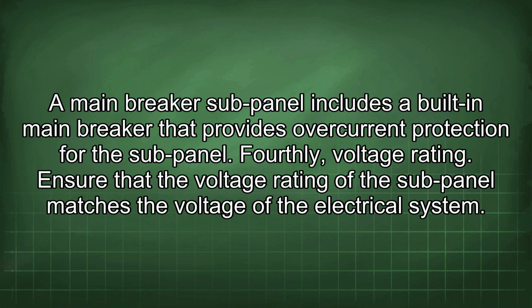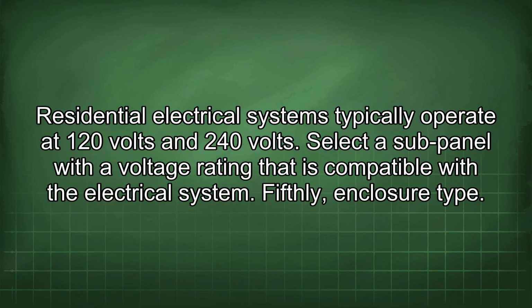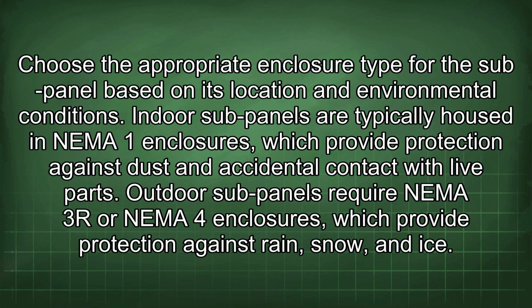Fourthly, voltage rating. Ensure that the voltage rating of the sub-panel matches the voltage of the electrical system. Residential electrical systems typically operate at 120 volts and 240 volts. Select a sub-panel with a voltage rating that is compatible with the electrical system. Fifthly, enclosure type. Choose the appropriate enclosure type for the sub-panel based on its location and environmental conditions. Indoor sub-panels are typically housed in NEMA 1 enclosures, which provide protection against dust and accidental contact with live parts. Outdoor sub-panels require NEMA 3R or NEMA 4 enclosures, which provide protection against rain, snow, and ice.